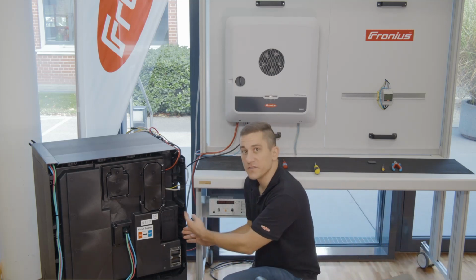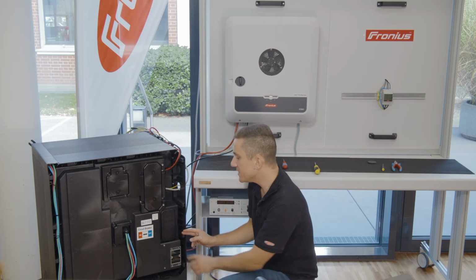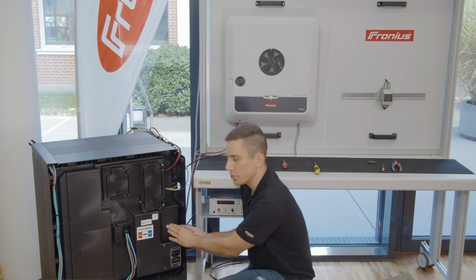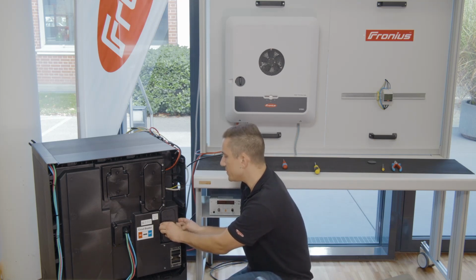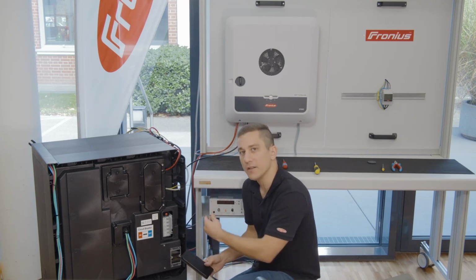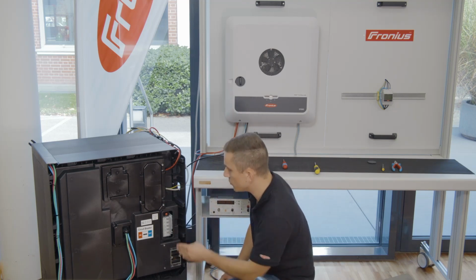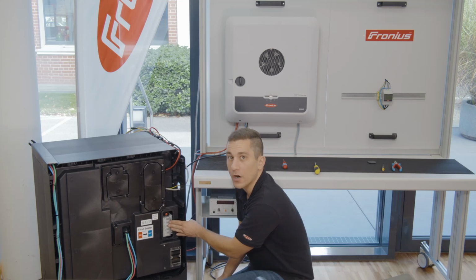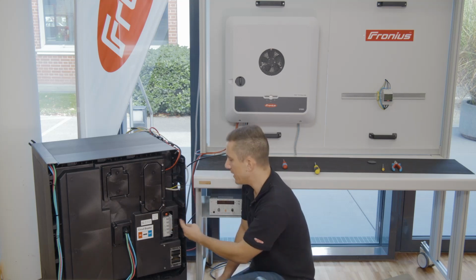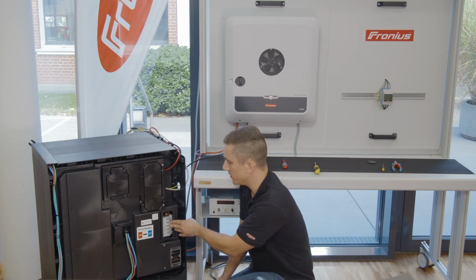After that, the first thing that you want to do is to remove the cover for the circuit breaker. Very important, whenever you are working on the battery system, please make sure that the DC switch is powered off. That means that there is no current on the battery system, and that means that you can safely work on the battery system.